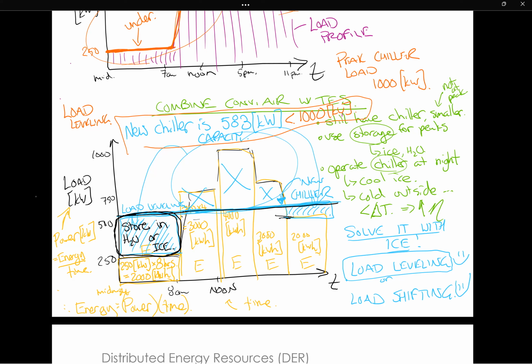I am just meeting this demand with my chiller here at noon. I'm undersized, that's fine, and now I'm oversized. This chiller is oversized, so I'm removing BTUs, removing joules, removing heat energy from ice, and building up the amount of cooling capacity of that ice. That's what I did with that smaller chiller, and that's called load leveling.